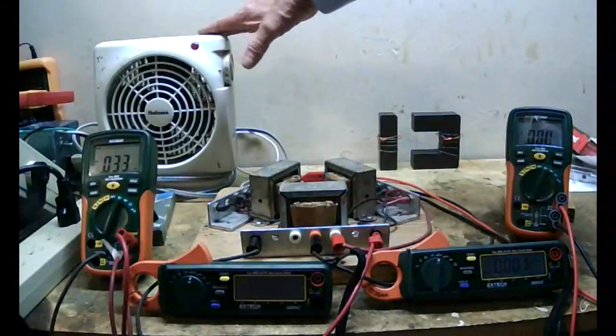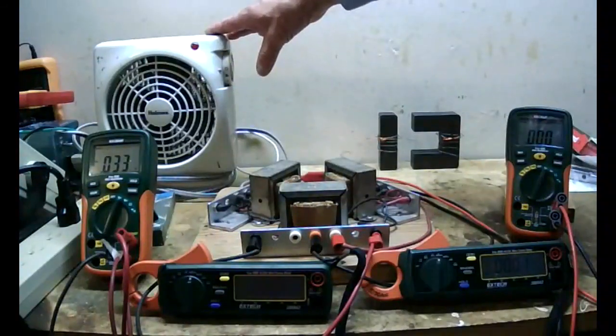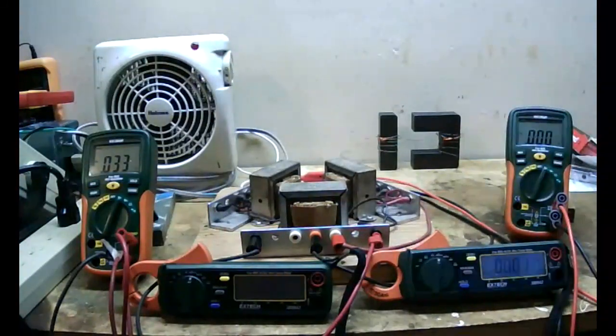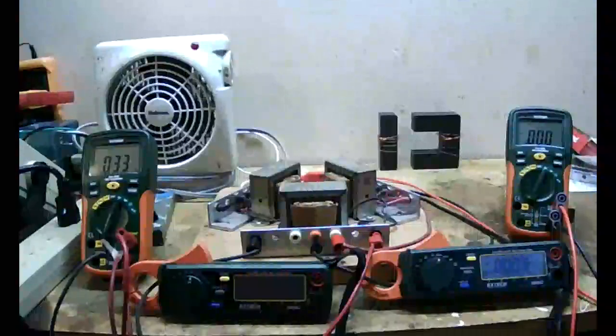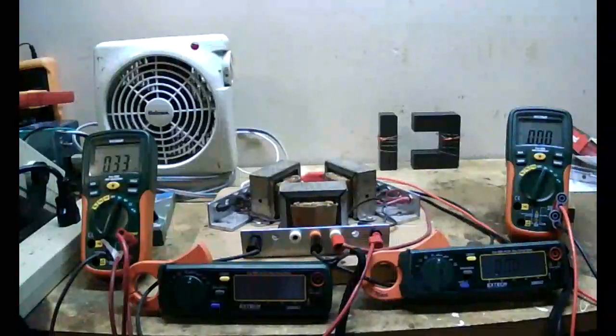In the back is a space heater. This is a mostly resistive load. It does have a small motor powering the fan. I'm operating this 120 volt heater at about 7 volts, so the fan is not going to come on. So we're going to have a mostly resistive load connected here, and it's a 1,000 watt heater, so it's a fairly large load, which means fairly small resistance. It's enough to let us do the demonstration on this transformer. So that's connected on the secondary side.